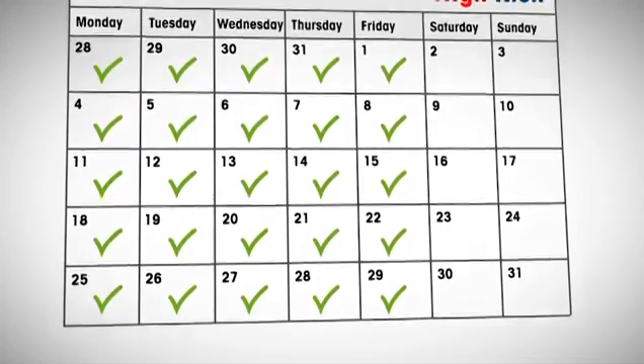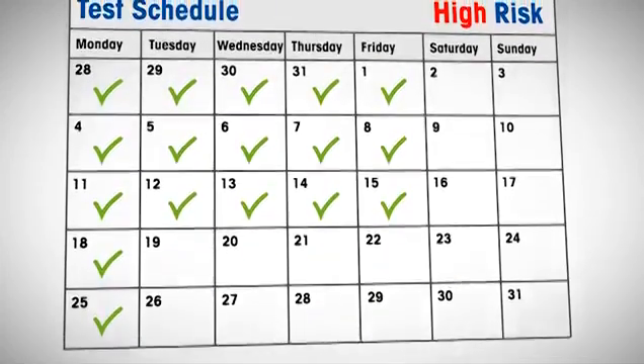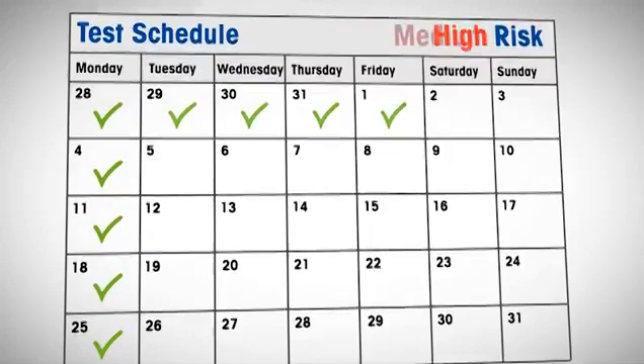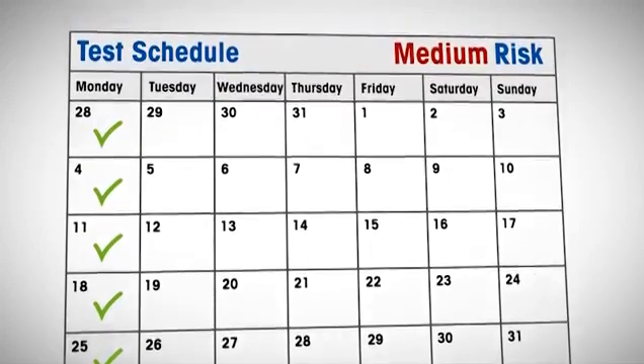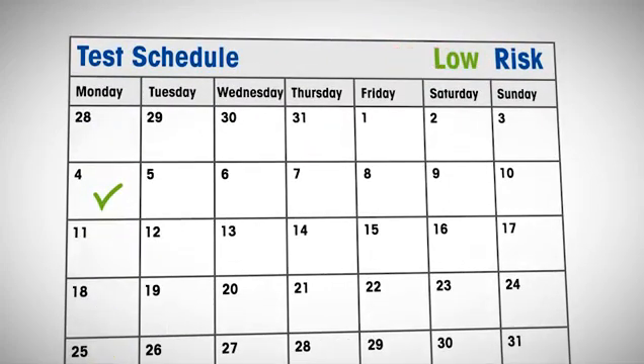Putting this strategy into practice means that daily or weekly testing, for example, would make sense for high-risk applications. For lower risks, however, less frequent test intervals can be implemented, allowing you to reduce unnecessary testing efforts without compromising compliance.